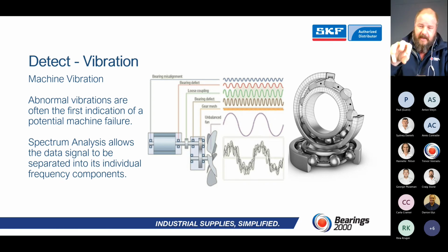Each bearing emits a different frequency depending on size, roller geometry, whatever the case may be, and we all just hear one thing. But when we look at the collection of vibration data, it gets split up into all the various sections that we need to understand. The spectrum analysis shows the data signal separated into individual frequency components. Now using words like spectrum analysis and frequency - if you're not into condition monitoring, or haven't yet worked with condition monitoring and vibration, these might be words that scare you, but it's not.